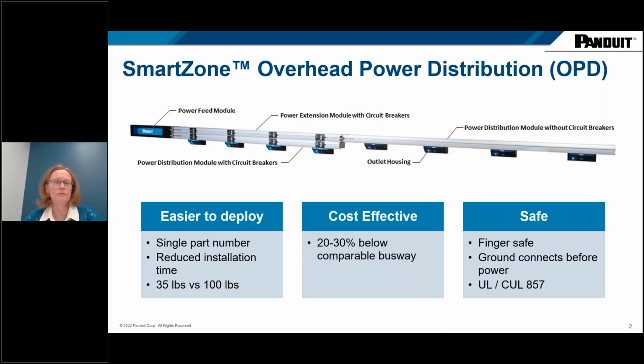This solution is much easier to deploy than, say, a busway system. It's just a single part number for a full 8-cabinet solution or a 4-cabinet solution, with significantly reduced installation time, as you saw in that video where Brian was able to connect the modules really just with a basic nut driver. It's lightweight, about 35 pounds per module, and very cost effective—we're targeting 20 to 30% below comparable busway solutions.